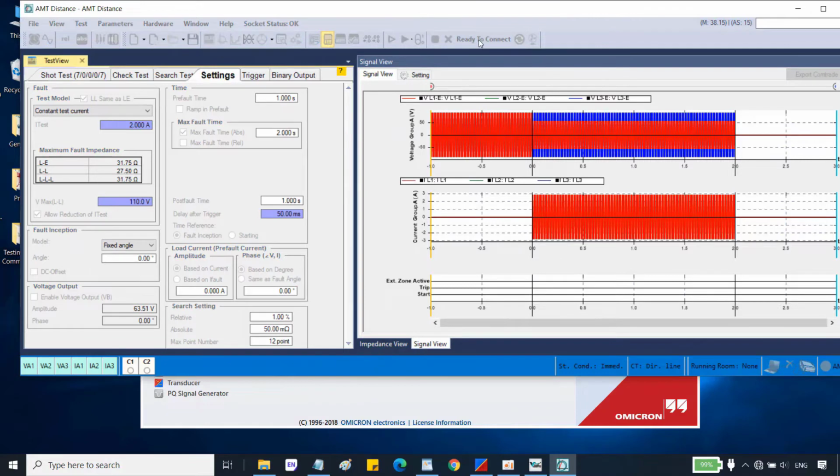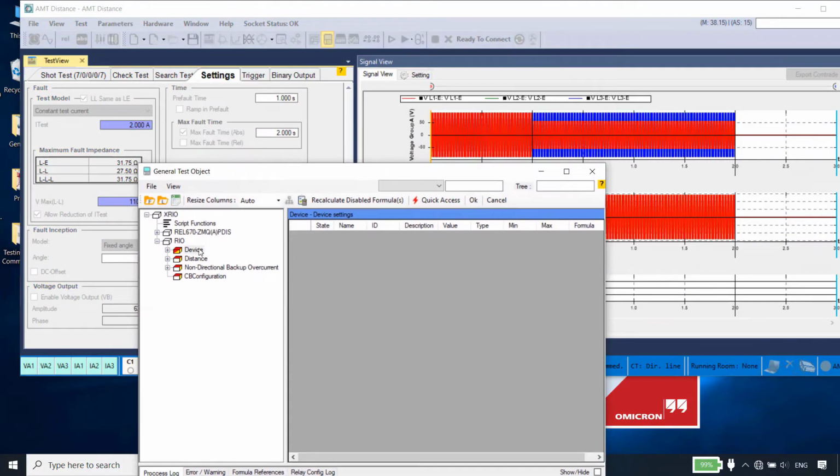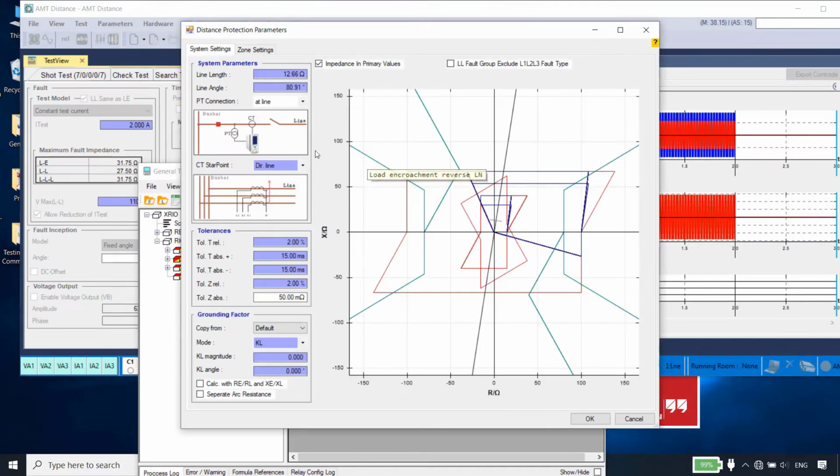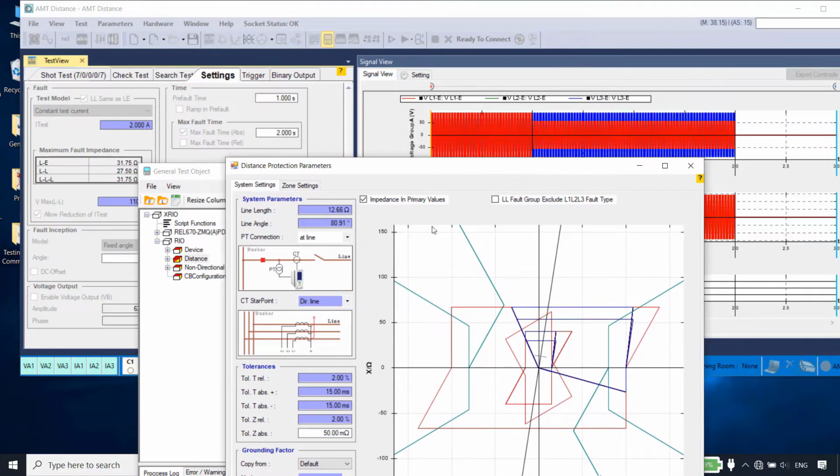And if we check them, and also if we select PT connected to the bus bar, then we will see there will be voltage in the post fault time. Yes, here we can see the PT after breaker. And if we select at bus bar, there will be.